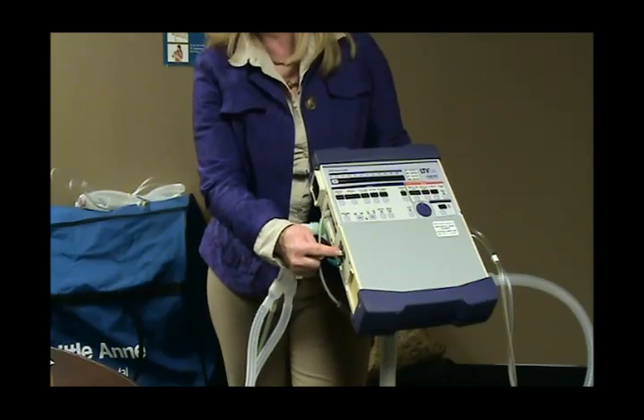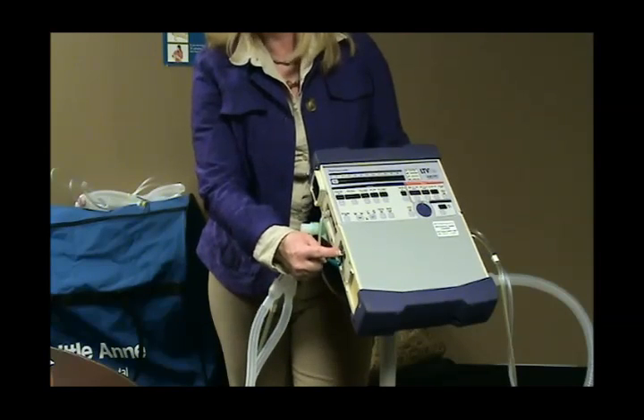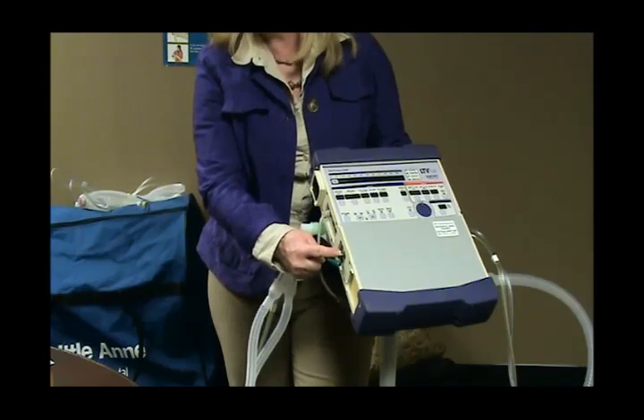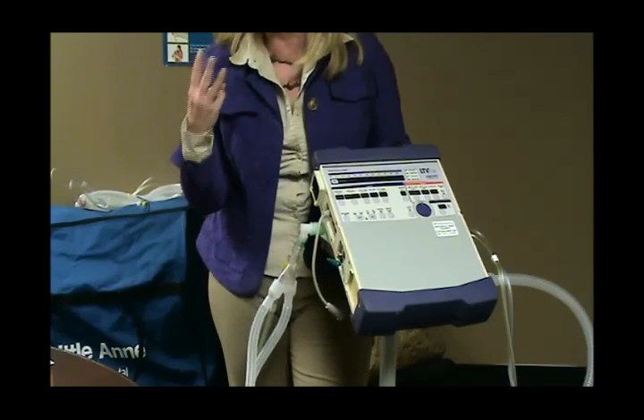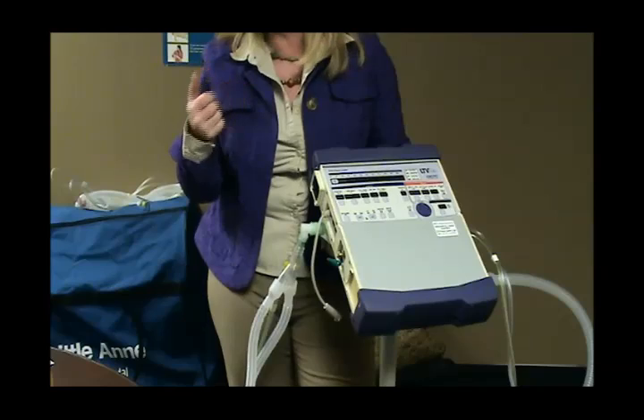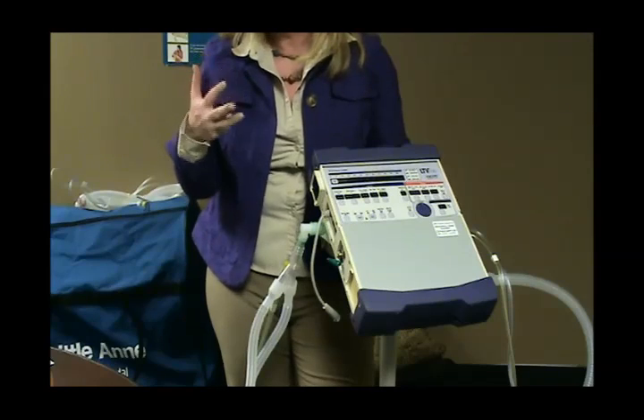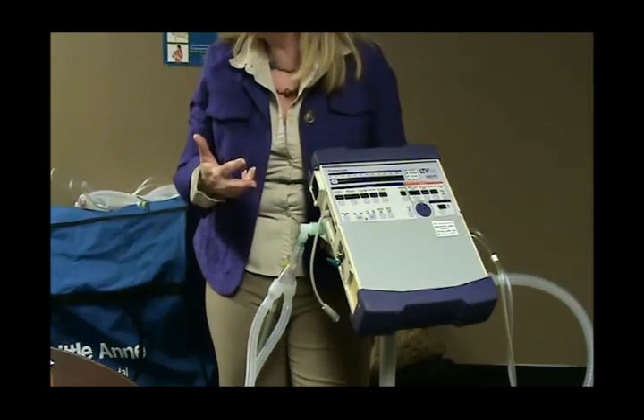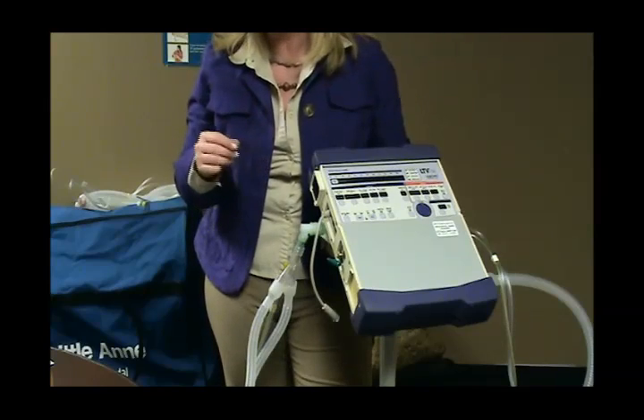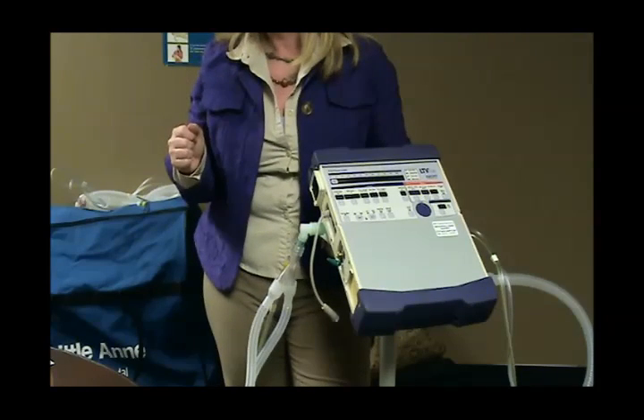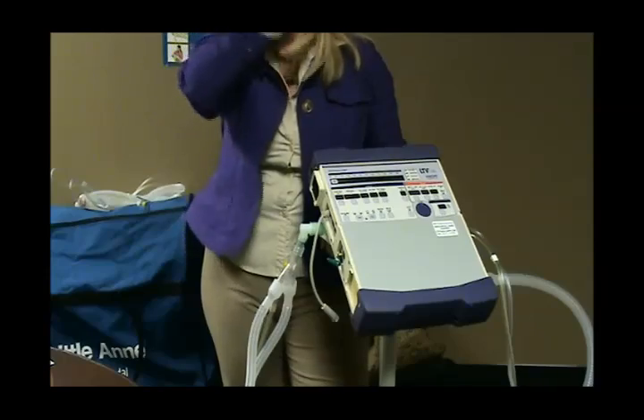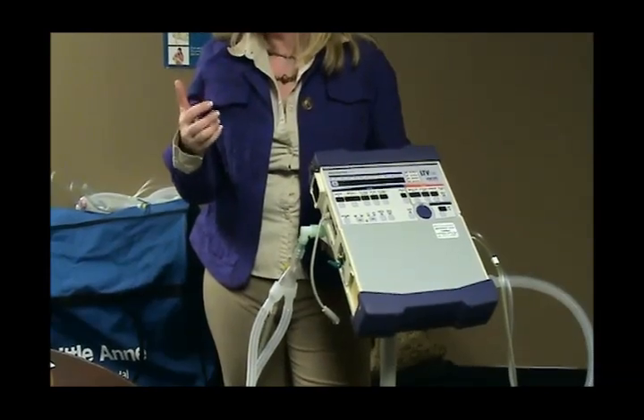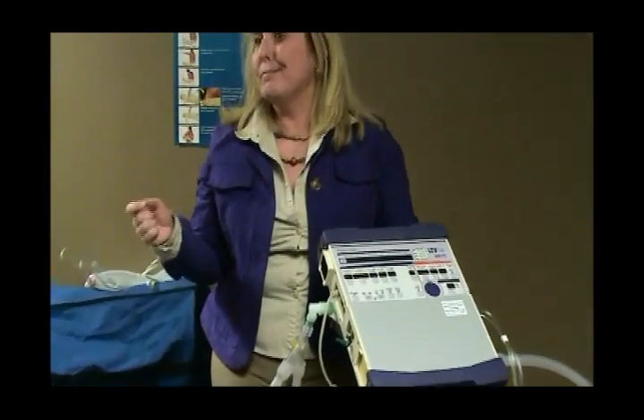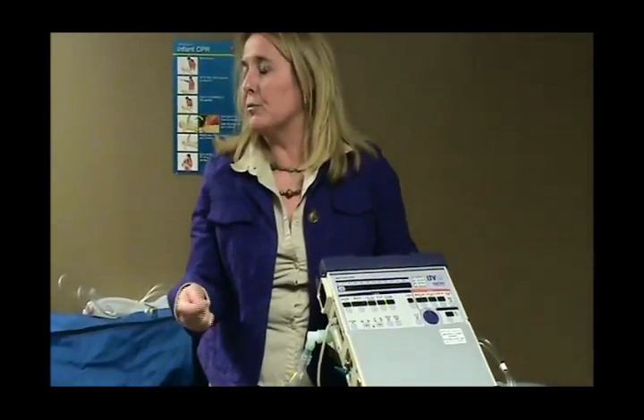Okay? Real quick mention about giving your oxygen into the ventilator with an oxygen concentrator. It's okay to do that, but you need to know what kind of concentrator you have. They usually come in 3 different types: 3 liter, 5 liter, and 10 liter machines. There are a few 7 liter machines out there, but not very many. Know what you're on, okay? And the reason is that if you have somebody who's on a 5 liter machine because they get their normal bleed in oxygen is either nothing or a quarter of a liter or something like that.